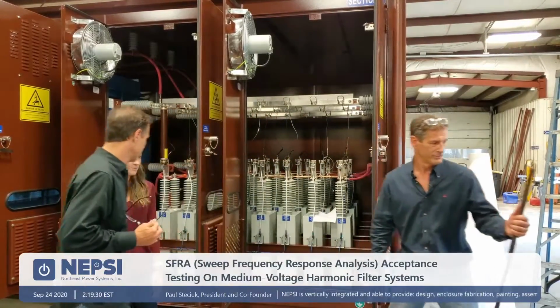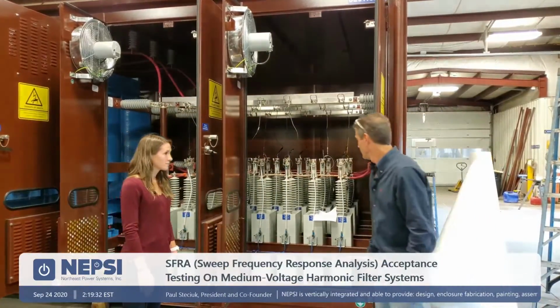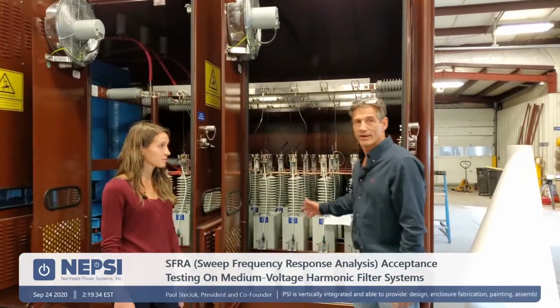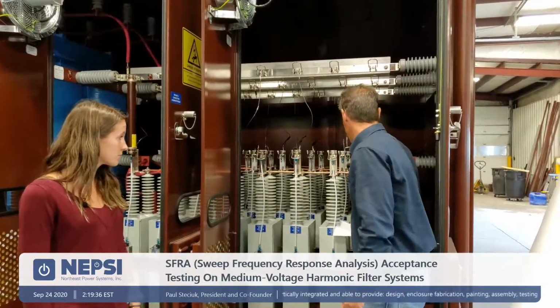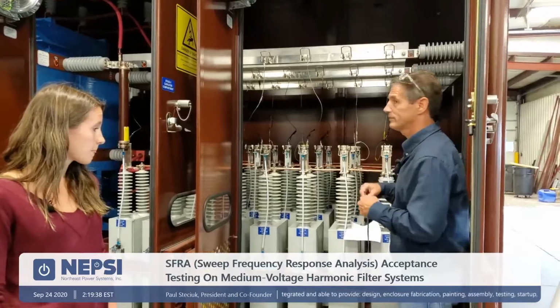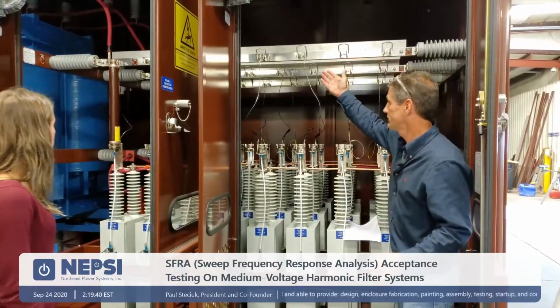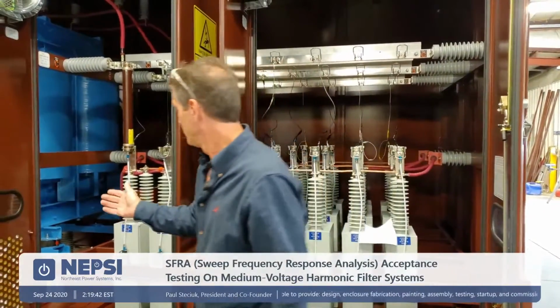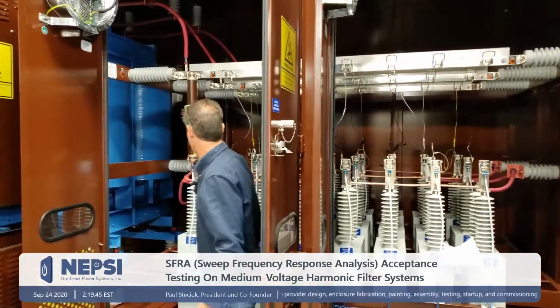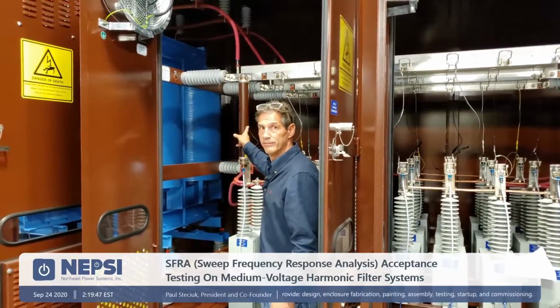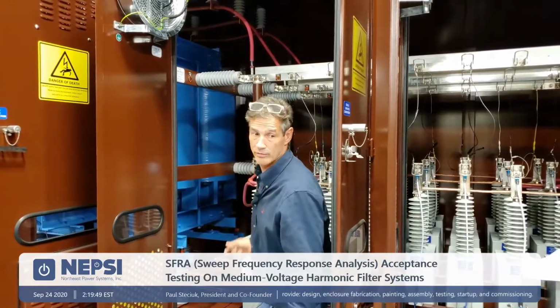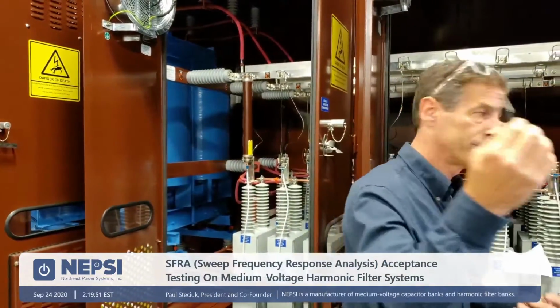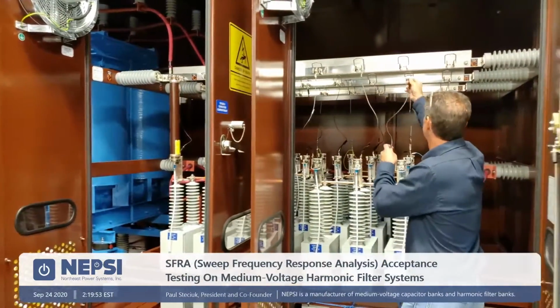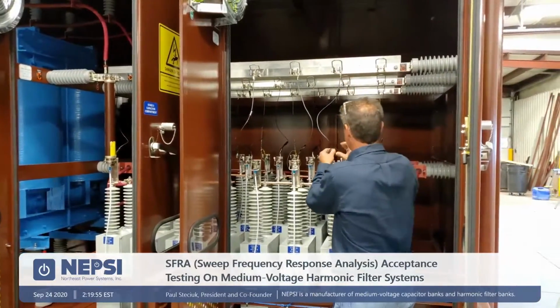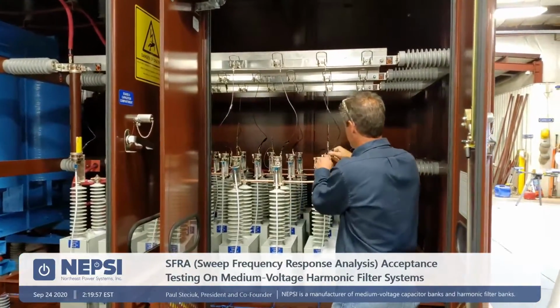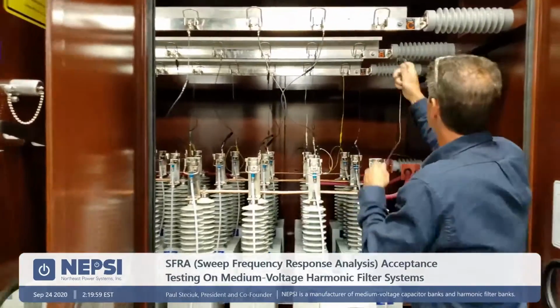All right. So we're just about done connecting up the capacitors. We have just two more capacitors to connect to what we call a collector bus here. The capacitors are connected to the collector bus through a fuse. And so rather than install all the fuses, we're installing jumper test leads between the collector bus and the capacitors. And I'll just get these connected up.